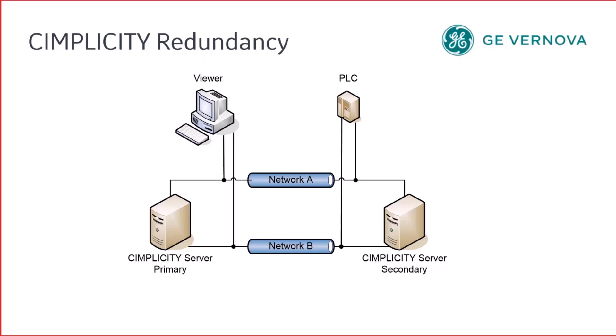In order to achieve server redundancy, CIMPLICITY has to make sure that all of the core processes between the primary and secondary are synchronized. This means they must have the same data and must be in the same state with regards to that data. This is achieved by setting up logical links between core processes on the nodes, with an active process and a standby process for each.